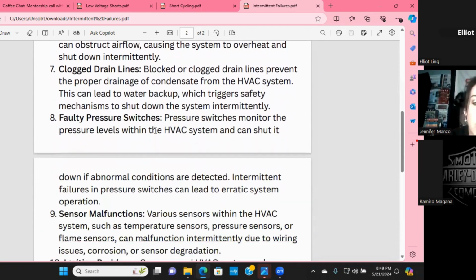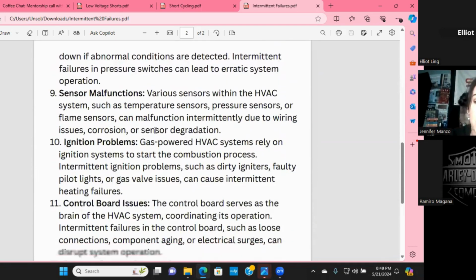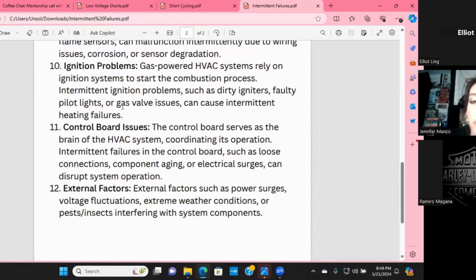Faulty pressure switches, we talked about. And then sensor malfunctions, ignition problems. This is where we talk about gas, but I wanted to just touch on this one a little bit. Control board issues. So I just want to give you guys one little tip that will go super far in your lifetime as an HVAC tech. If it's one thing that the system is doing that's not correct in the sequence of operations, it's not your board. If there's more than one thing, it could be the board.